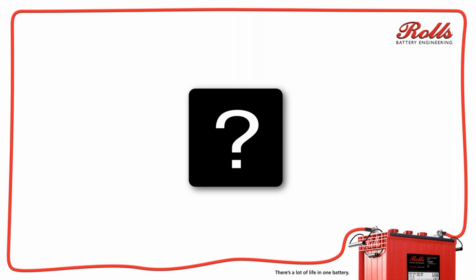Okay, so Julian DeMarte asked a couple questions. He has a client that was using a Series 4500 level indicator on a Series 5000 battery. He's gotten them the correct level indicators, but will that have caused any issues? Yes. If it's not the correct level indicator for the correct battery, you could either overfill the batteries or you could underfill the batteries. Of course, underfilling the batteries will cause problems with exposing the battery plates to corrosion.